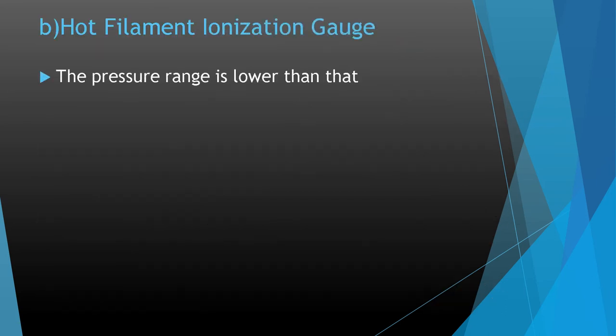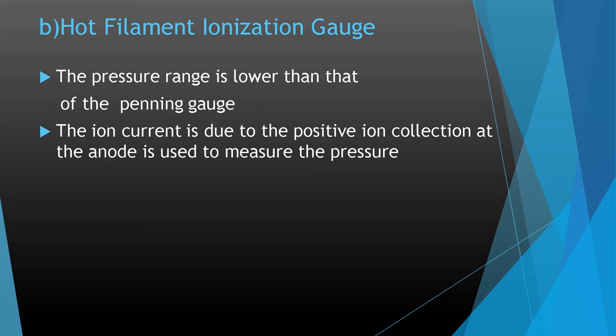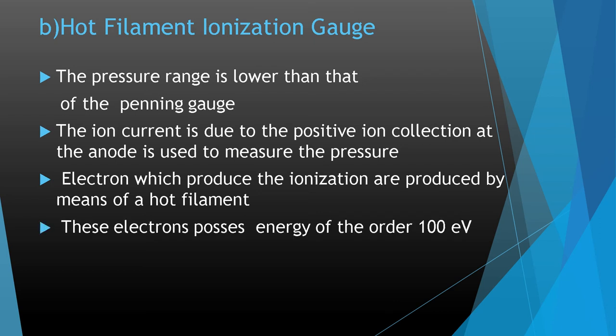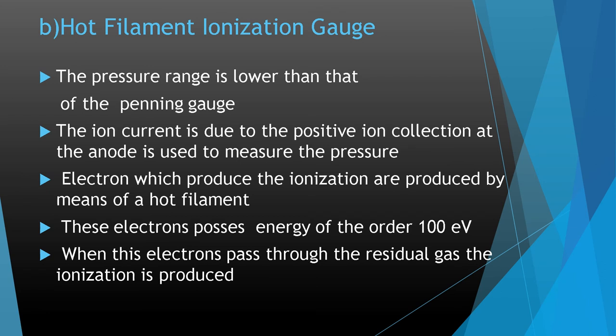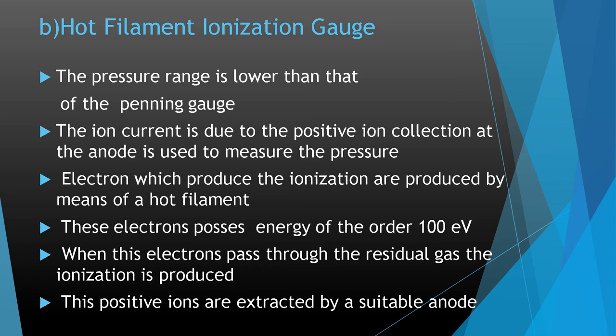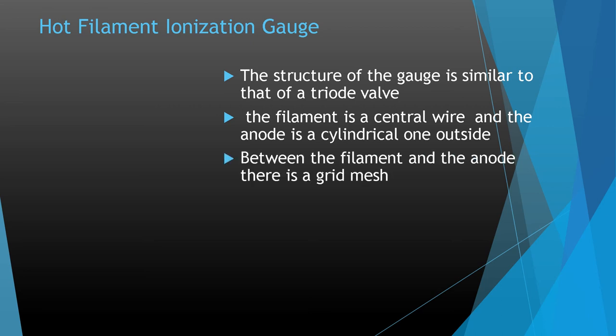The ion current due to positive ion collection at the anode is used to measure the pressure. In the hot filament ionization gauge, the electrons which produce the ionization are generated by a hot filament and possess energy of the order of 100 eV. When these electrons pass through the residual gas, ionization is produced, and the positive ions are extracted by a suitable anode. The structure of the gauge is similar to that of a triode valve — the filament is the central wire, the anode is a cylindrical structure outside, and between the filament and the anode there is a grid mesh.